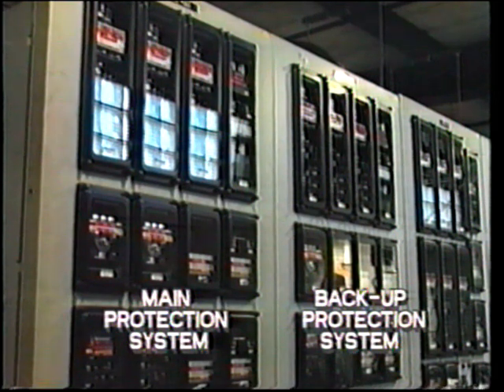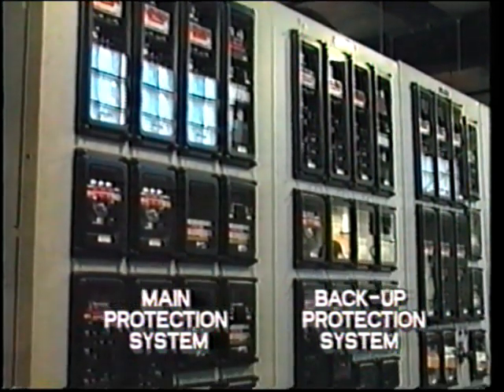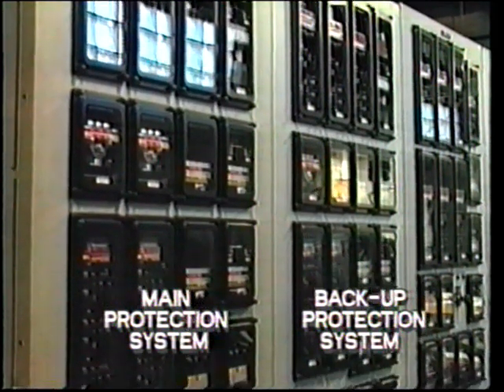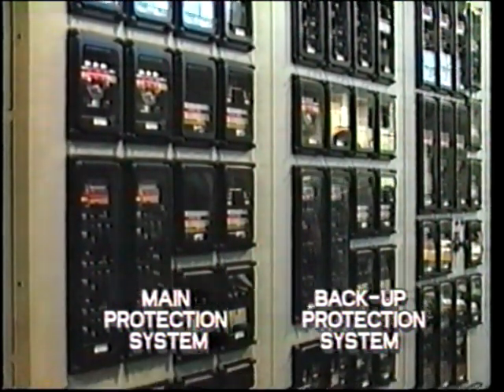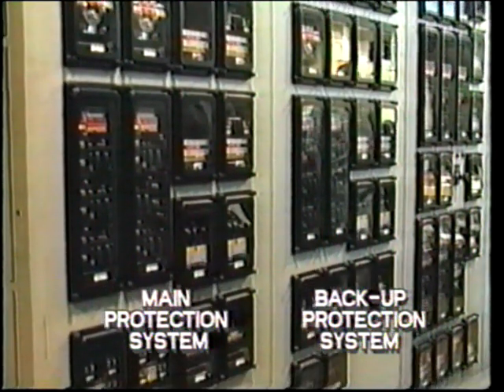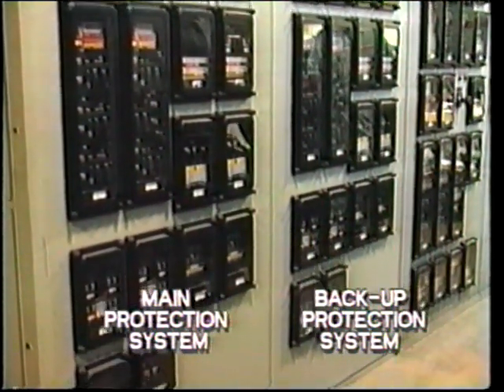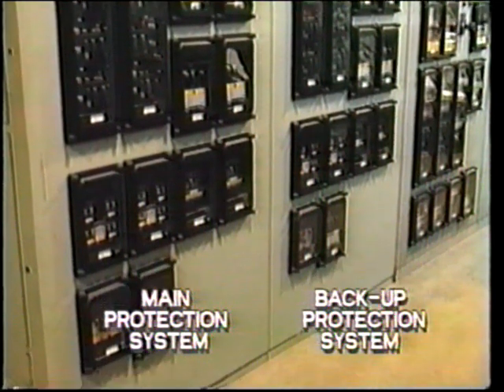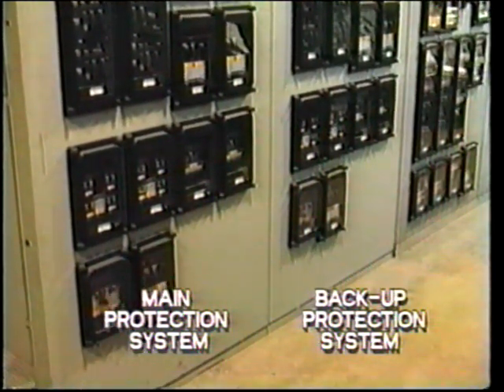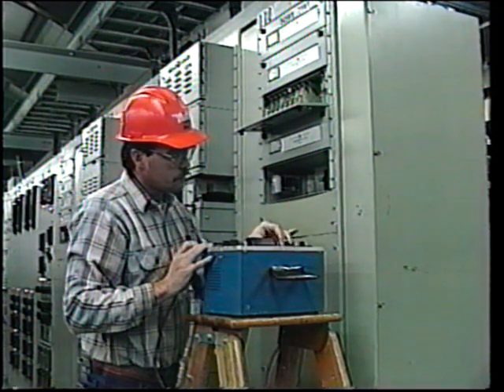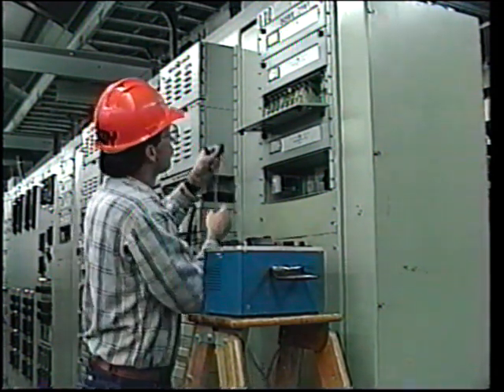The major issue is that as the line remains in service, it must continue to have some protection equipment still operable. Frequently, high-voltage transmission lines are equipped with duplicate protection schemes, including duplicate CTs and duplicate tripping coils in the breaker cabinets. In this situation, one complete set of protection can be removed for testing while the other package remains in service. Even with this arrangement, testing will be conducted with the least number of relaying components out of service at any one time. Many pilot relaying schemes include duplicate communication channels.